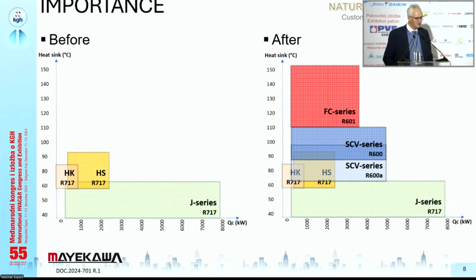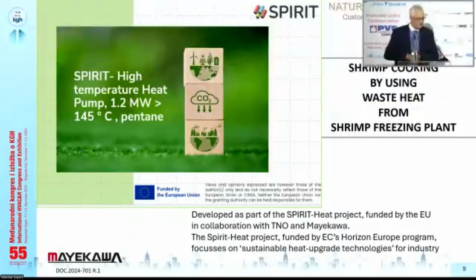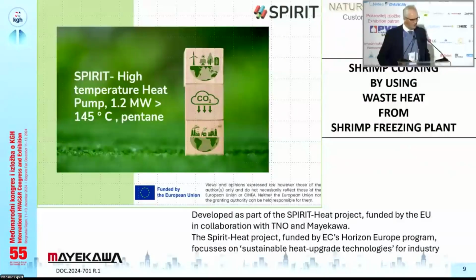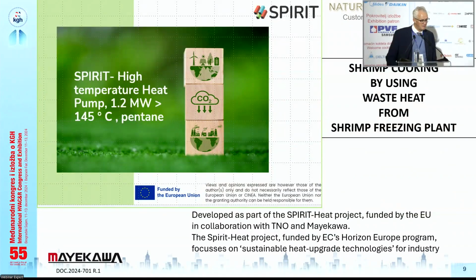So if we look before, and I speak about the past 100 years, we had, of course, our ammonia applications with our ammonia compressors. You see on the bottom, the J-type series, it is used up to 65 degrees condensing, 67. So it means minus 2, 3 degrees is your water outlet, what you can obtain in that system. Then we have our HK. It is around 85 degrees condensing, and the HS is about 90, 92 degrees.